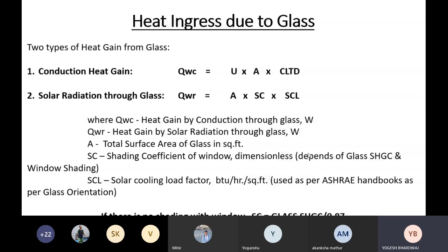So shading coefficient again is there, dimensionless. It depends upon my glass SHGC or my window shading. It depends on both the things. Then solar cooling load factor varies from orientation to orientation, and I can directly take the values for SCL as per my location from ASHRAE guidelines. If there is no shading and we have the glass SHGC value, we can divide the SHGC by 0.87 to get the shading coefficient value.